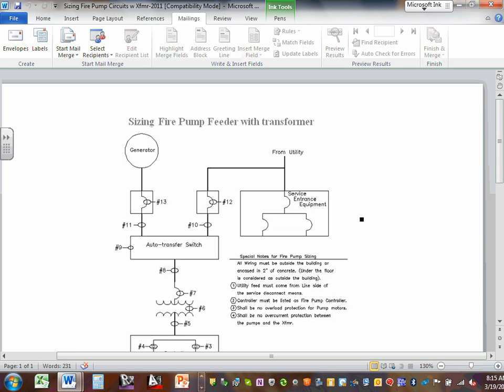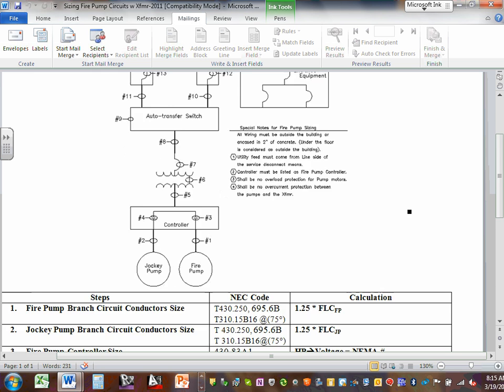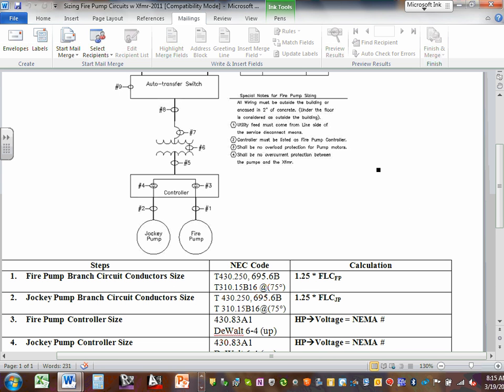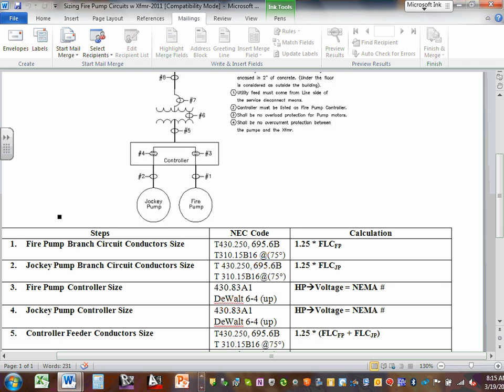If your voltage system is 480 and your fire pump is 208, what do you need to do? You need to transform the voltage. So what would you do if you have a transformer? It's a special case. Let me walk you through the same thing from the bottom. Look what happened. Start from the bottom. The first 1 and 2, the branch circuits, are identical to what we have done. No change. Can you guys see that?